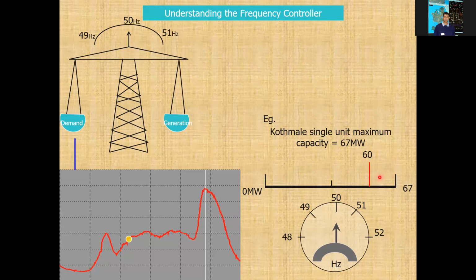Because now, for example, in this time, the generator has only 7 megawatt margin to increase, but you are still in the increasing portion of the load curve. As a result, system operators always keep an eye on not only the system frequency, but also on the output of the power station that is doing the frequency controlling. When they notice that the frequency controlling station has reached one of its limits, they will intervene and change the output of some other power station so that the frequency controlling station always comes back to its mid region.